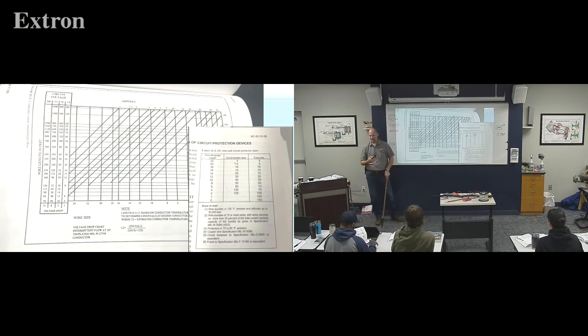So a 10 amp circuit breaker means you can function at a constant 10 amp, or is that going to break at 10 amps? Are you trying to confuse me? I know, so the way to read the chart is I know what size wire I have, what breaker do I need to protect it? So if I know I have an 18 gauge wire, what circuit breaker do I need to protect it? It's going to be that size or smaller because we're protecting it. So an 18 gauge, I can put a 10 amp circuit breaker in to protect it.